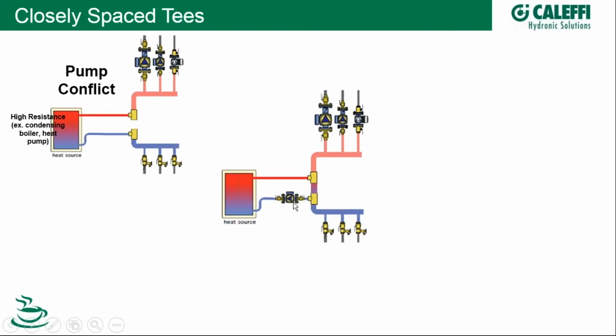We have to add another pump here, otherwise the path that we have just created for flow from the secondary circulators by way of this connection bridge here, if you will, would be causing bypass and not flow going through the boiler. You would be starving the boiler. So you have to have a primary pump, primary, secondary. Now this improves pump conflict, but it doesn't eliminate it.